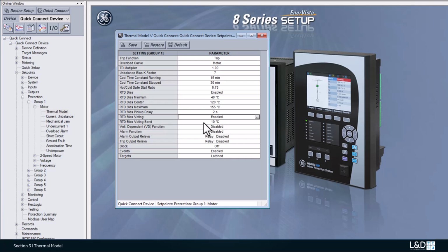The RTD voting band specifies the temperature difference range between the maximum stator RTD temperature and another voting stator RTD temperature. The volt-dependent VD function is used for the high inertia load, and we can just disable this function in this example.